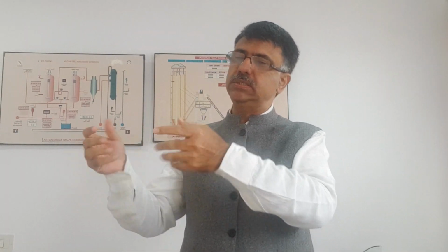So we have to install the CTs plus this Solcon. Yes. The toughest part is taking out the client's cables, putting in the CTs and then putting the cable back. That is the toughest part. If the client already has CTs available, or if he agrees to put in the CTs, you just connect them and bring the cable to Solcon. The distance between Solcon and the CTs should not be more than 10 meters in any case.